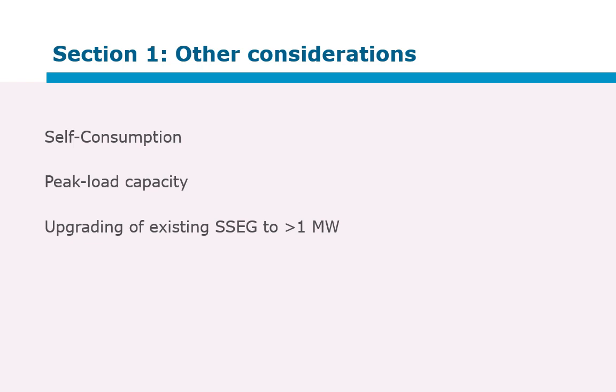Where an application for an embedded generator is in addition to an existing system, and the total system size exceeds 1 MW, the entire process should be followed for the total size. For example, an existing installation of 600 kW applies to double the capacity. It is not a new application for 600 kW, but an application for 1.2 MW, and the customer and distributor need to follow the entire process listed in the guide.